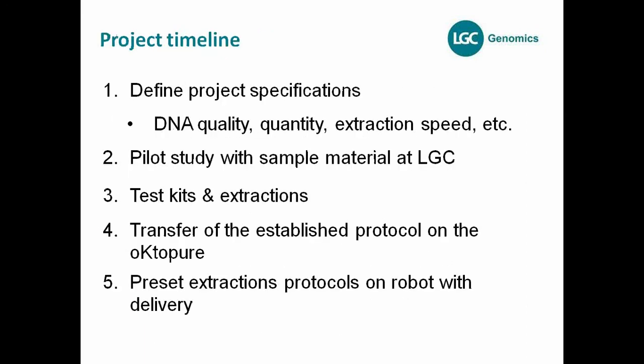Regarding project timeline — every project is different. Therefore, we like to define the project specifications at the beginning: what kind of DNA quality you need, what quantity, extraction speed, and what else is important. We can then decide which technology and robot to recommend, and proceed to a pilot study, developing the protocol in-house for you. We send you the protocol, DNA for testing, and a test kit so you can repeat the protocol we've developed, then transfer established protocols to the oKtopure or GeneSpin. You receive an instrument with preset extraction protocols already on the robot.